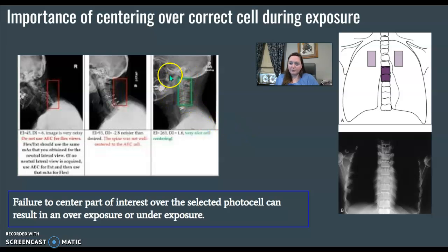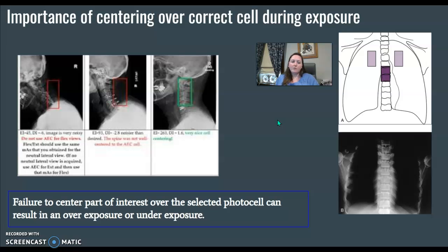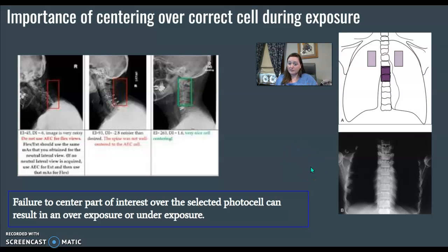For lateral cervical spine, we don't use photo cells or photo timing for C-spine, because the likelihood that you're directly over that cell is fairly slim. If you get that anatomy right over that cell, it's going to help you and give you an accurate image. But if the part is in front of that cell and there's basically air there, it's going to shut off too early and you're going to get an underexposed image. So if technologists fail to center the part over the cell or choose the wrong cells, we're going to get an error.